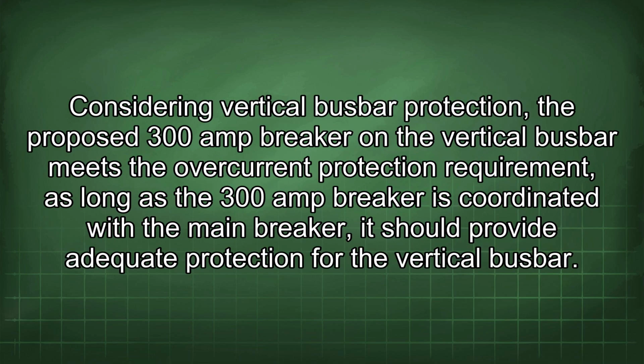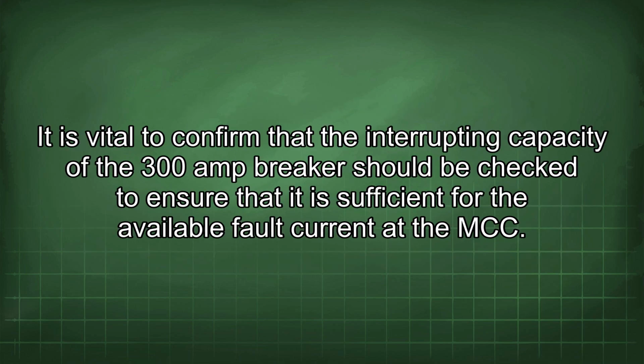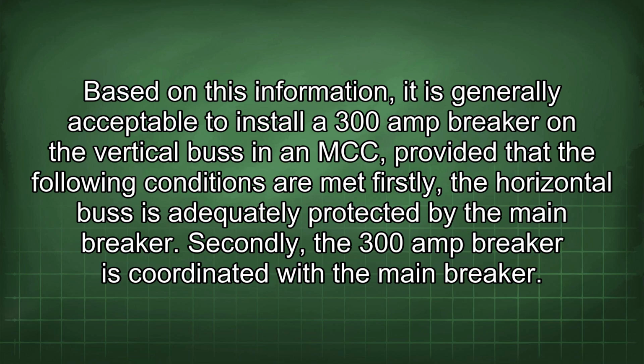Considering vertical busbar protection, the proposed 300 amp breaker on the vertical busbar meets the overcurrent protection requirement. As long as the 300 amp breaker is coordinated with the main breaker, it should provide adequate protection for the vertical busbar. It is vital to confirm that the interrupting capacity of the 300 amp breaker is sufficient for the available fault current of the MCC. Based on this information, it is generally acceptable to install a 300 amp breaker on the vertical bus in an MCC, provided that the following conditions are met.